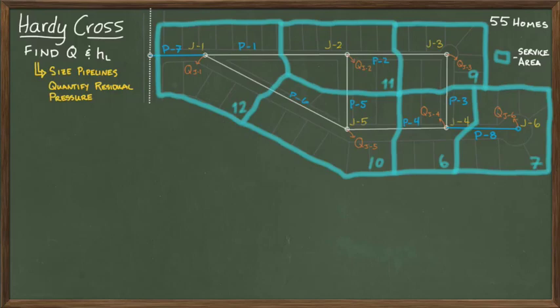We are ready to begin the analysis with step one, where we analyze the hydraulics of pipe seven, starting with identifying the flow rate in pipe seven, which is just the total flow rate of the system. Once you have the flow rate, then you can find the diameter of the pipeline using the maximum velocity criteria or the maximum head loss criteria, or both.